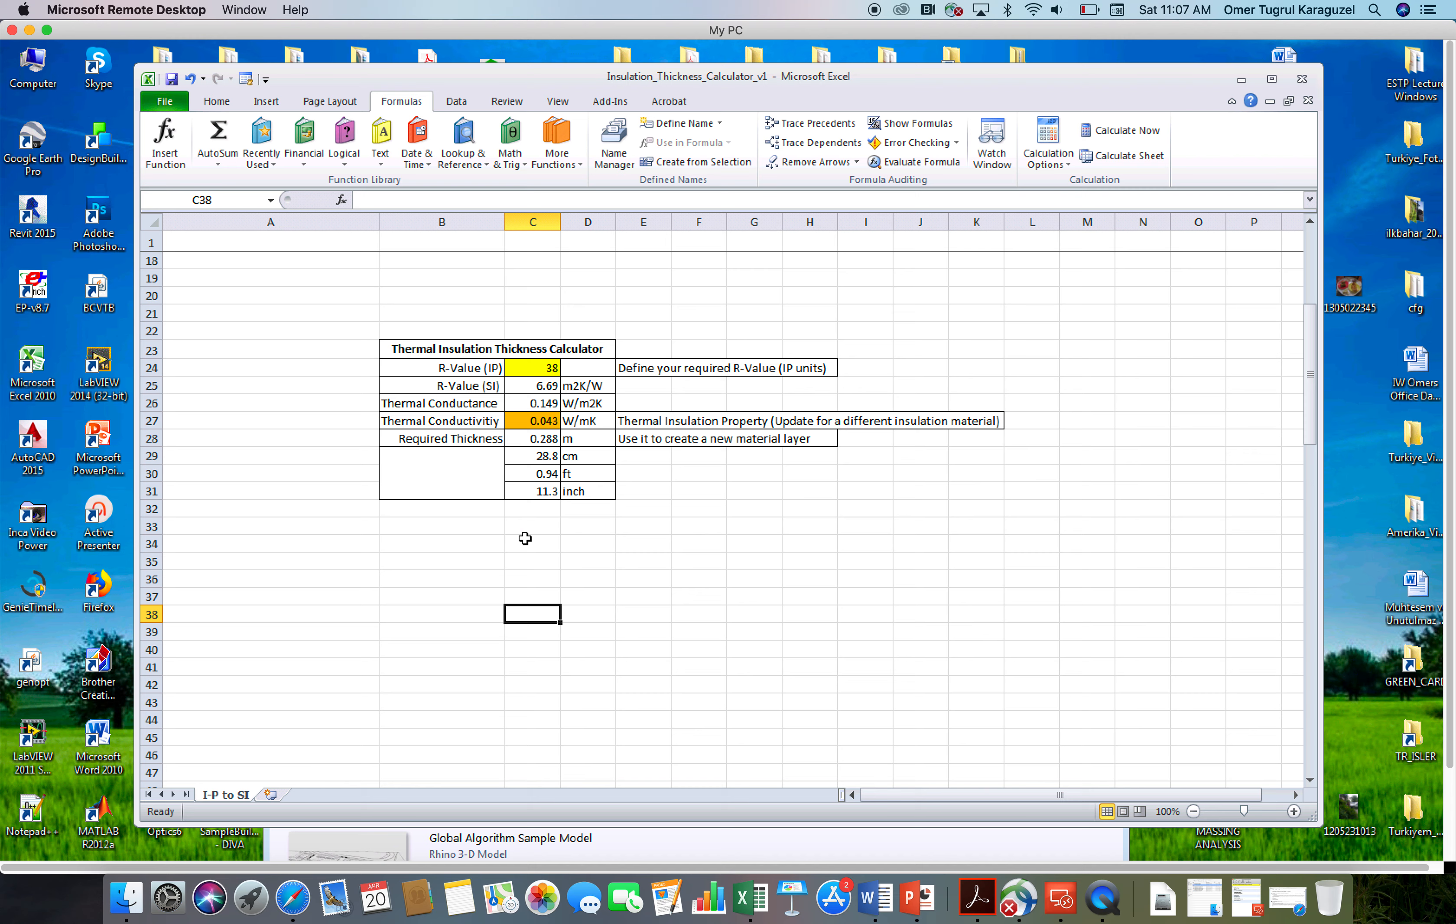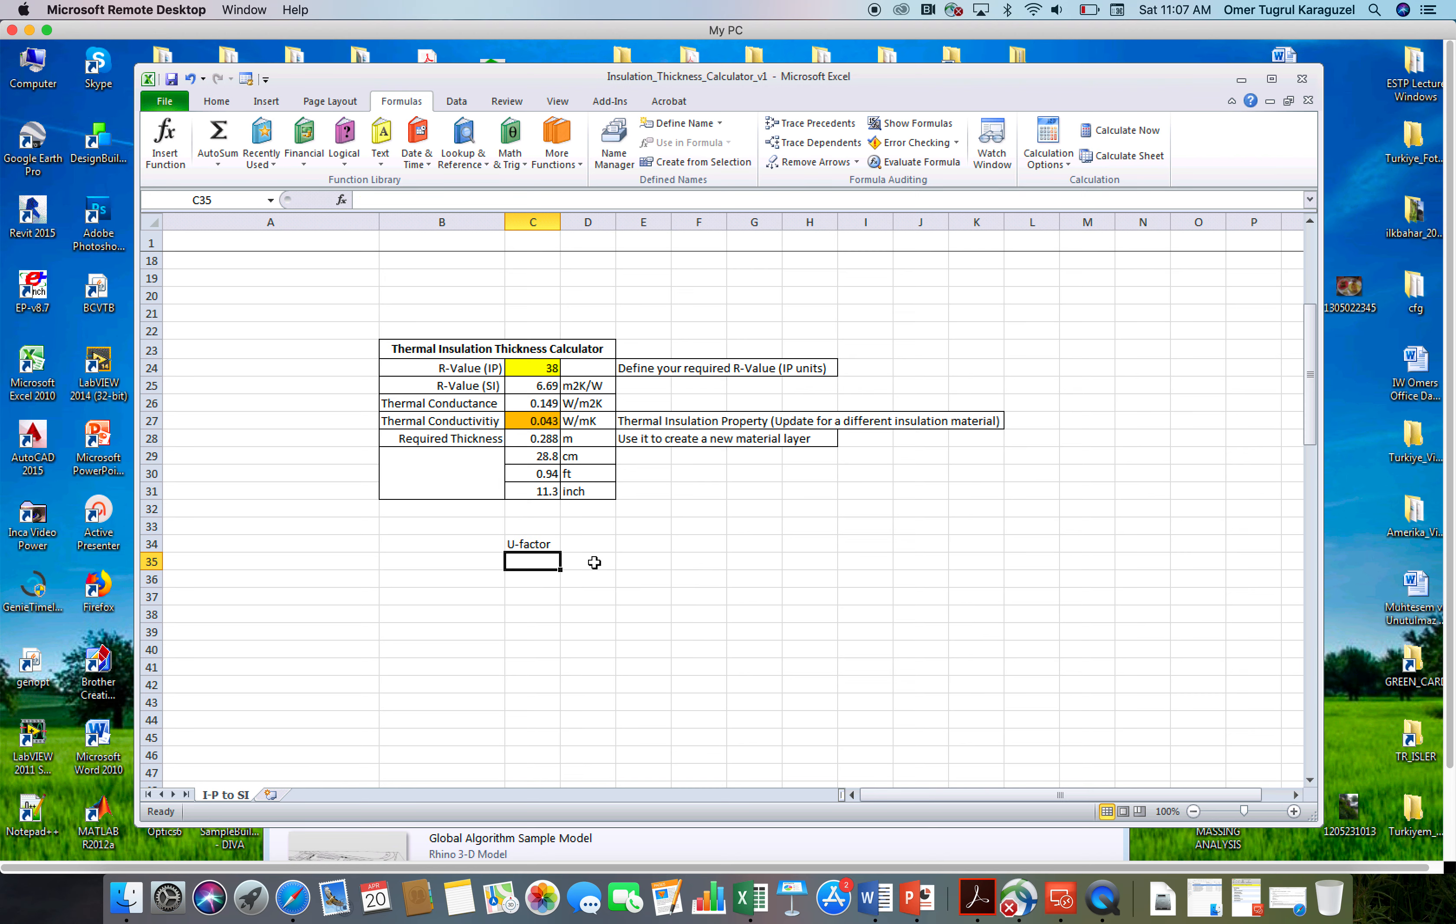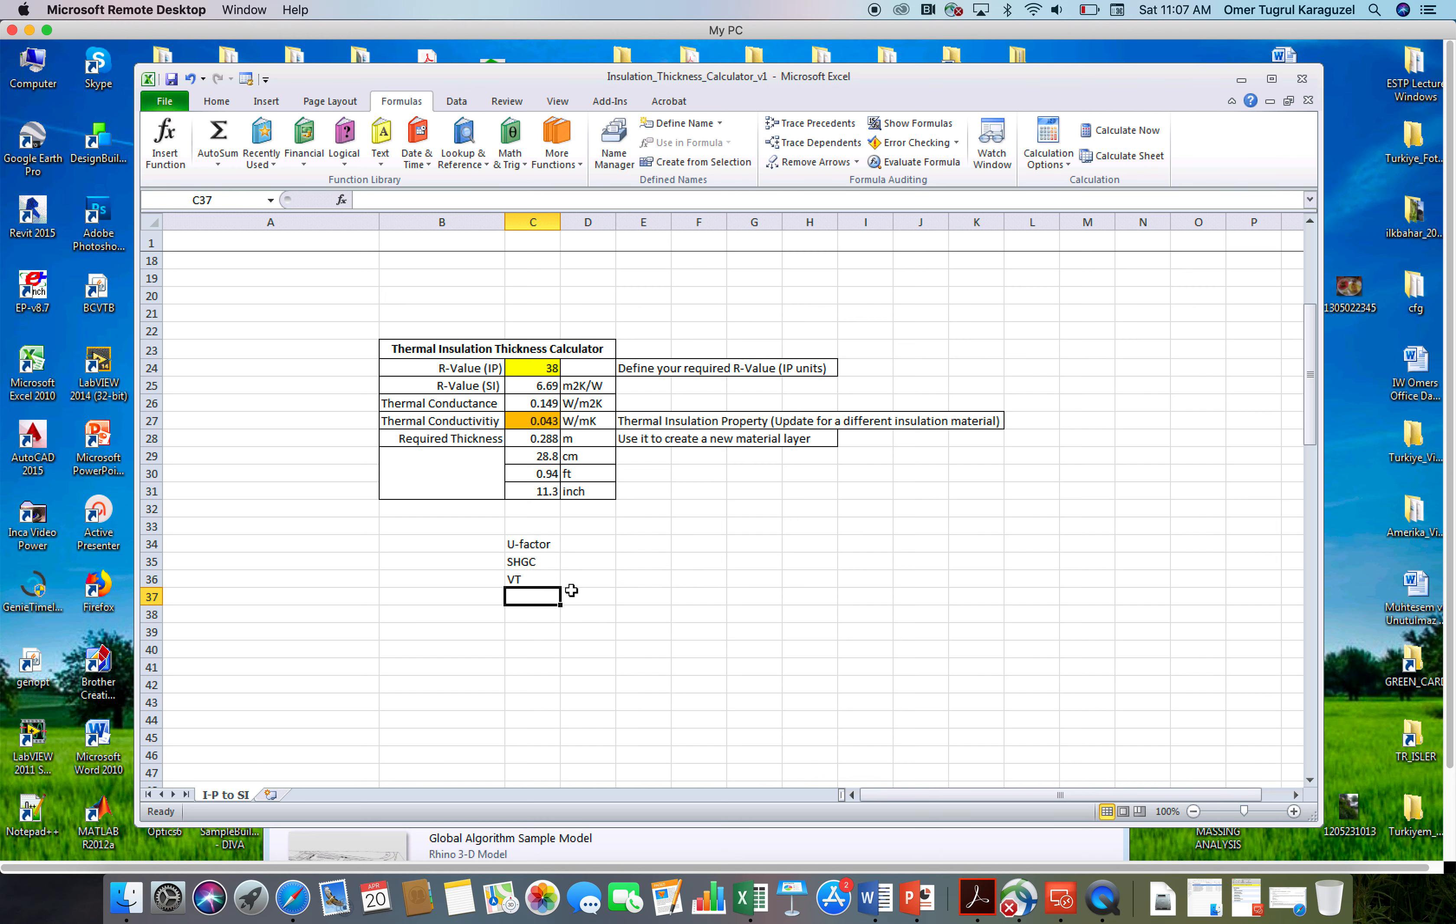So this is all I have today. I hope it will be helpful for you guys to update the global algorithm. But again, remember, you can do it for walls. You can do it for roof. You can do it for the floor assembly, slab on grade assemblies, or even for the glazing. For the glazing materials, you don't need these calculations, but you need to find out the U factor of the new window assembly, solar heat gain coefficient of the window assembly, and visible transmittance of the window assembly. If you find out these three pieces of information, you are good to go to create a new glazing assembly. There are no conversions or calculations needed, but some research needed to find out what could these values be for the glazing. But for the opaque assembly, this calculator will be really helpful for you guys to finish your job.